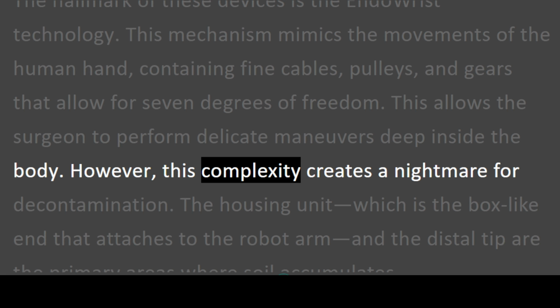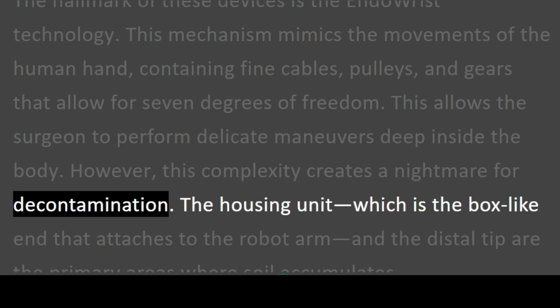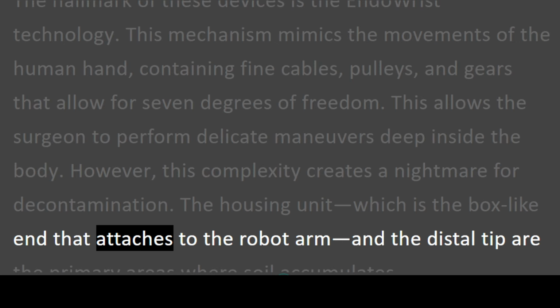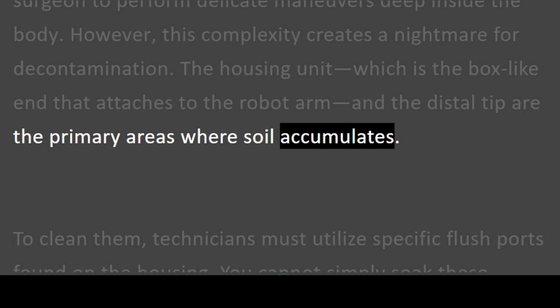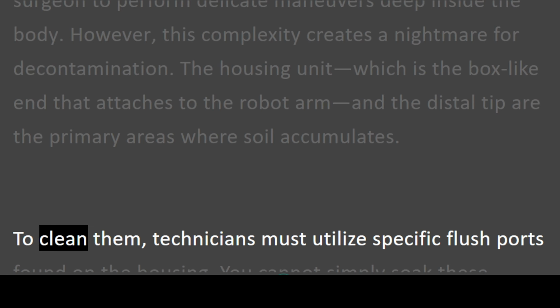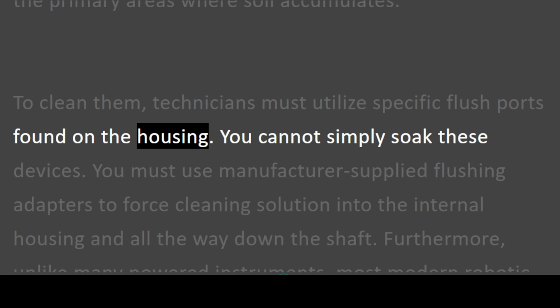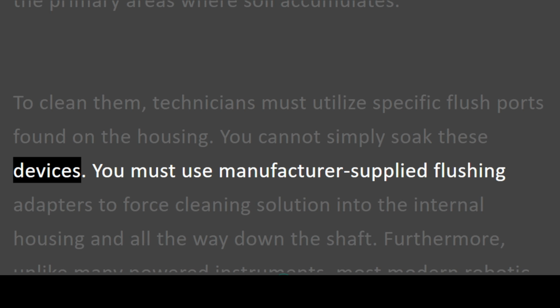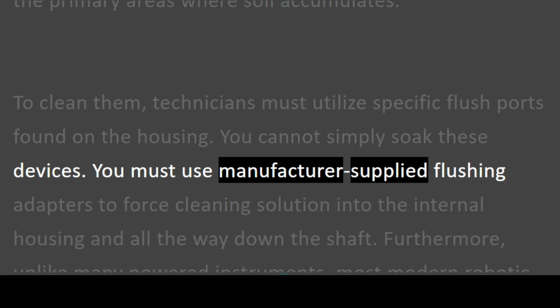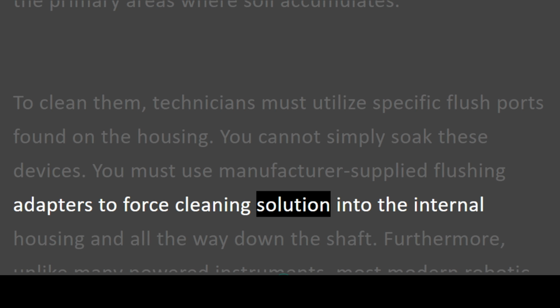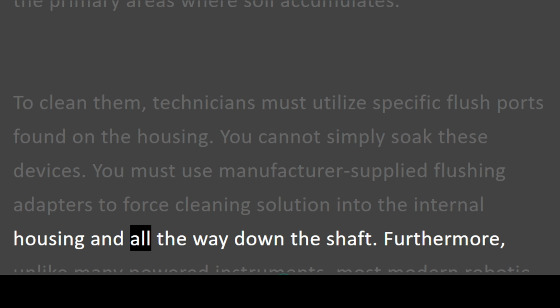However, this complexity creates a nightmare for decontamination. The housing unit, which is the box-like end that attaches to the robot arm, and the distal tip are the primary areas where soil accumulates. To clean them, technicians must utilize specific flush ports found on the housing. You cannot simply soak these devices. You must use manufacturer-supplied flushing adapters to force cleaning solution into the internal housing and all the way down the shaft.